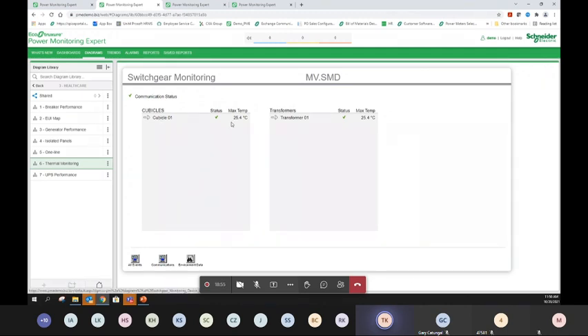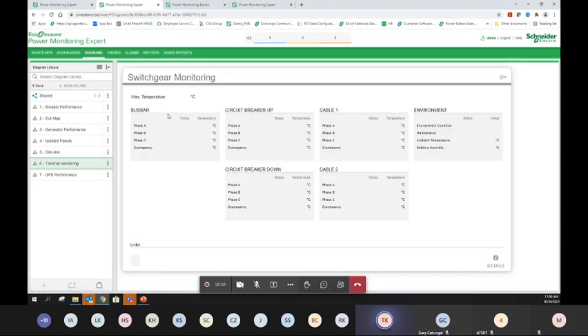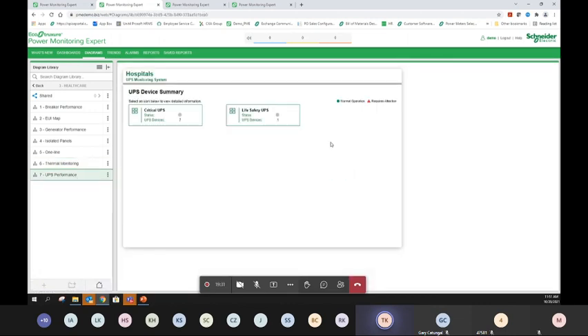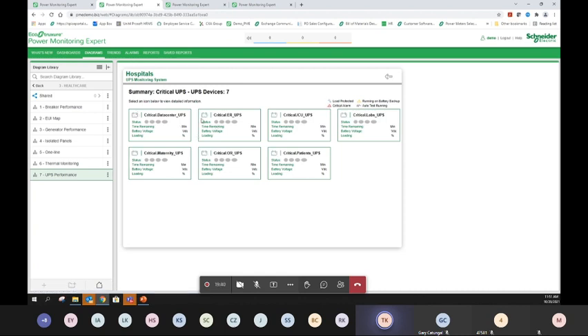You are able to have all the detailed parameters of the voltage and the current against the temperature rise. Any abnormalities, it will show you the alarm in the software. So this is one of the applications to help with the safety against electrical fire, rather than loose joints causing a fire if you are waiting for the yearly optical test. So the same thing, we have this kind of graphics that you can have. Again, these are highly customized graphics. You can create as many as you like.